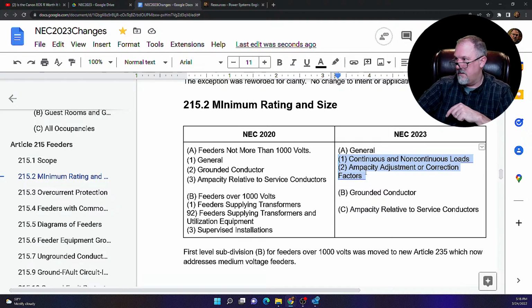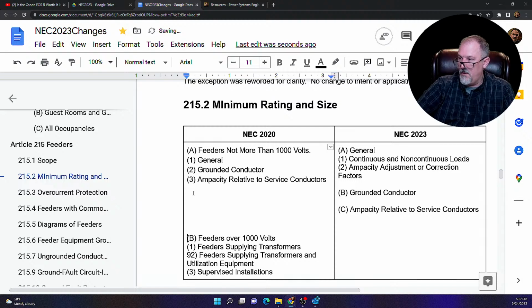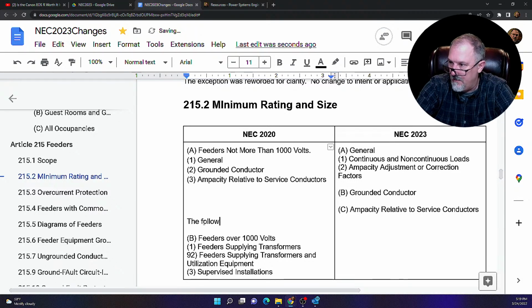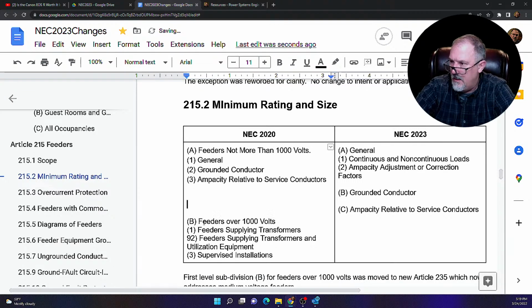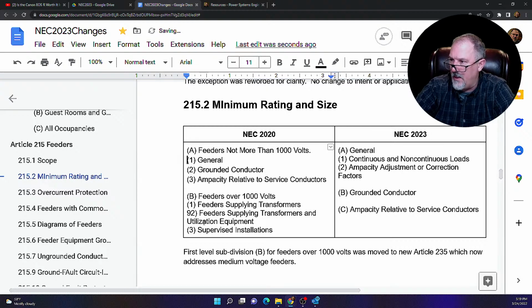It looks like ampacity relative. Let's take a look at what ampacity relative to service conductors used to say: the feeder conductor ampacity shall not be less than that of the service conductors. The feeder conductor ampacity, that's now C. So that became C. Grounded conductor became B. So all of this was moved, and we're going to say the following was moved. I say that down below, I'm not going to put it in twice. All right, so that's what we got. A.